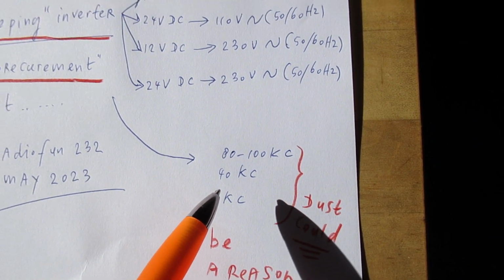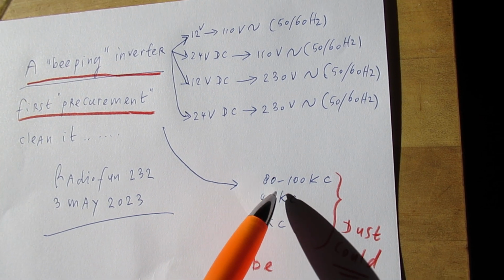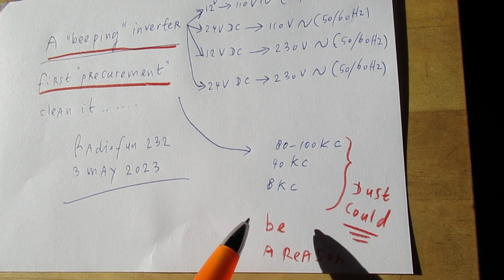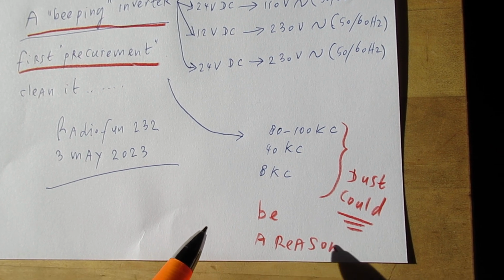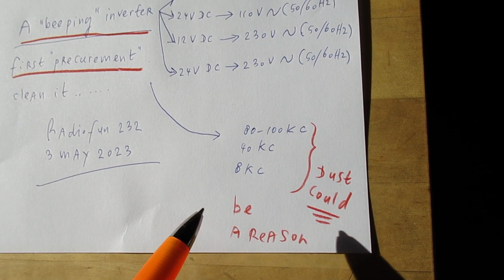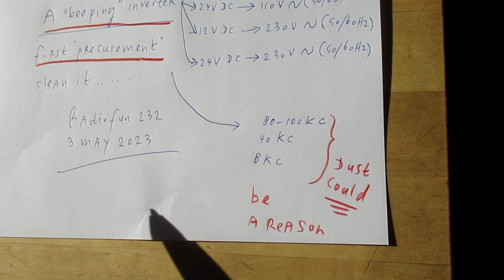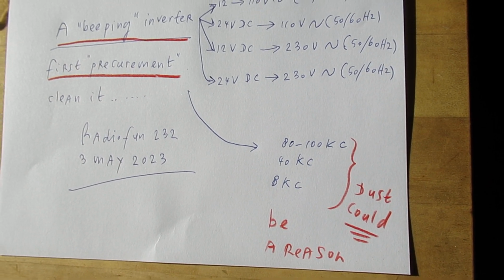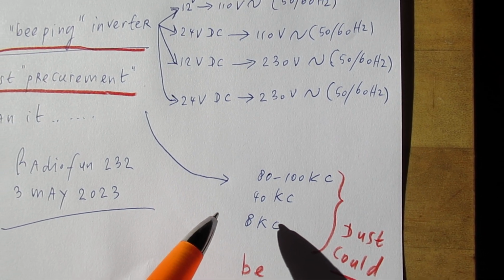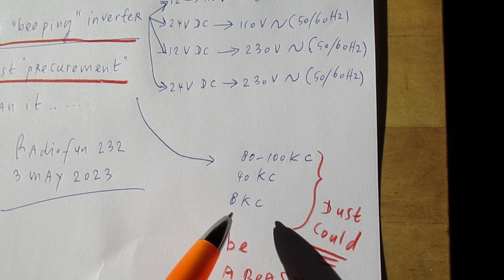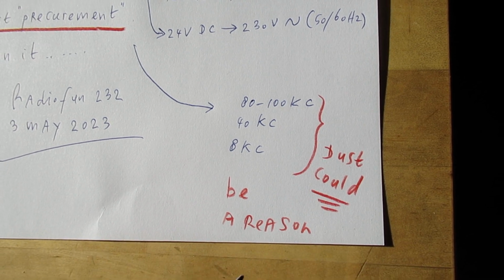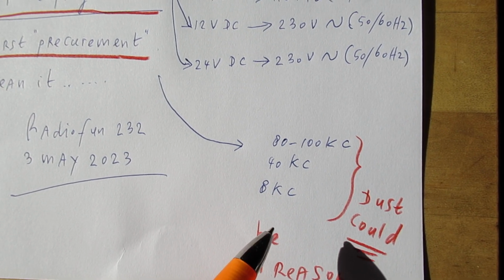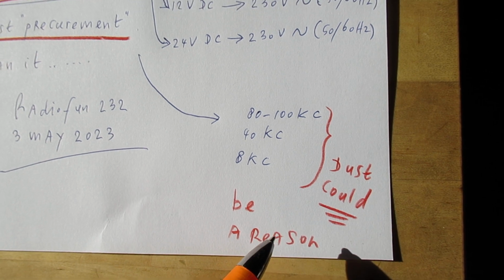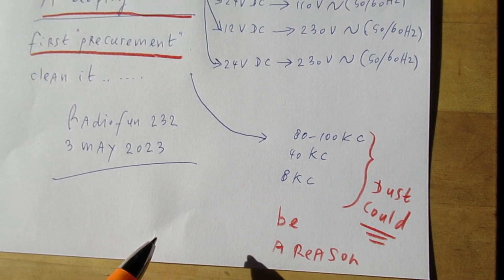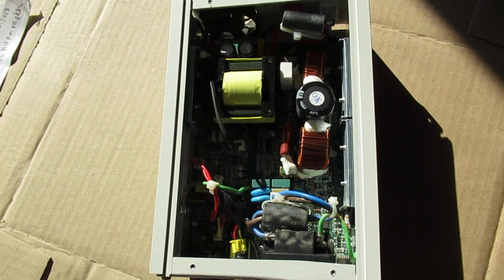When that frequency goes down, of course you cannot hear 80 kilocycles, that's impossible. The human ear can only receive up to approximately 18 kilocycles. But when that high frequency is damped due to dirt, etc., the frequency will go down and you can hear it.